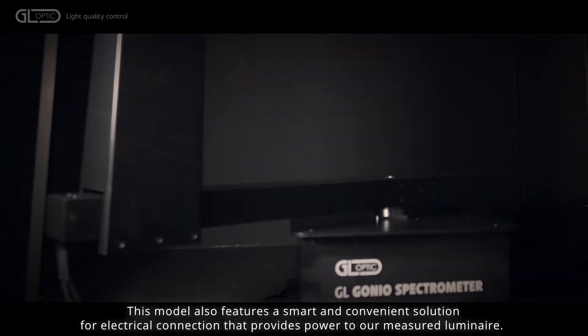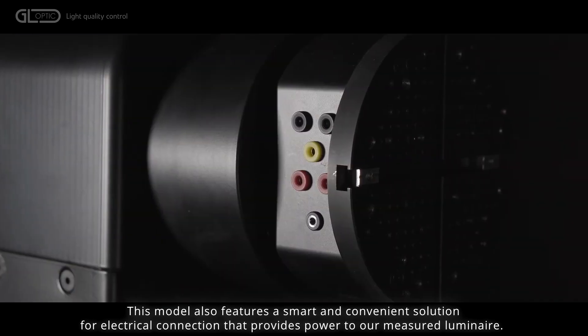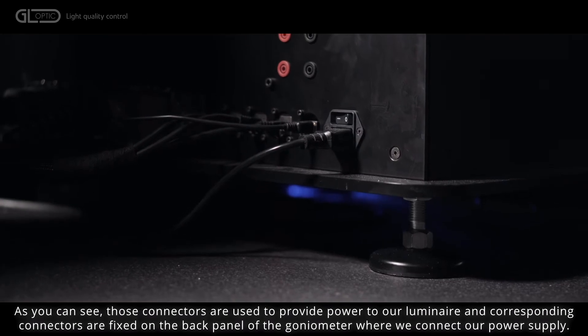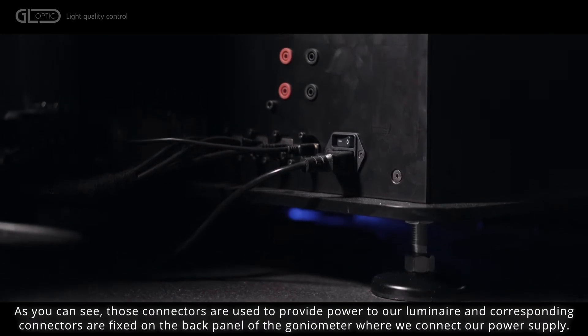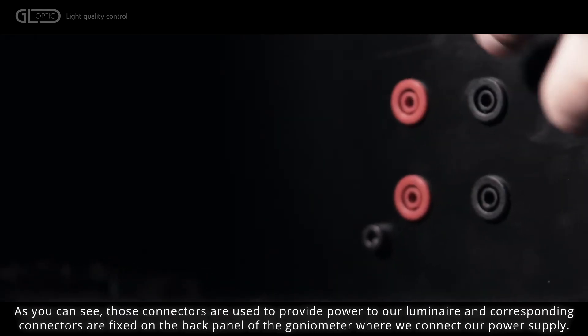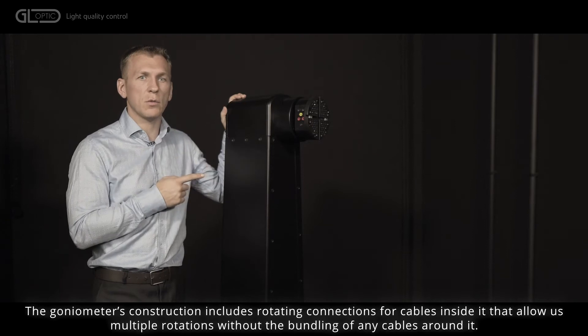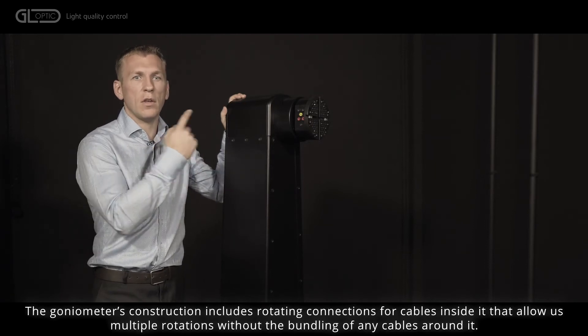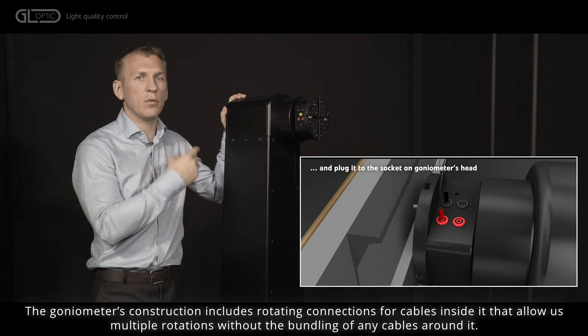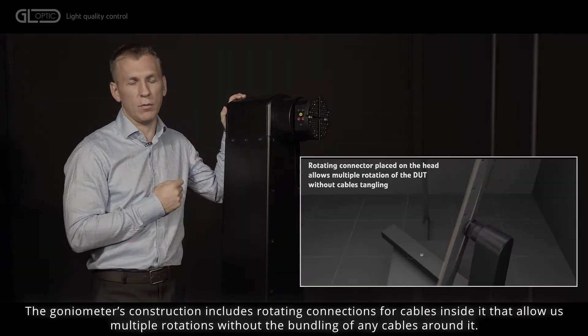This model also features a smart and convenient solution for electrical connection that provides power to the measured luminaire. As you can see, those connectors are used to provide power to our luminaire, and corresponding connectors are fixed on the back panel of the goniometer where we connect our power supply. The goniometer's construction includes rotating connections for cables inside it that allow multiple rotations without the bundling of any cables around it.